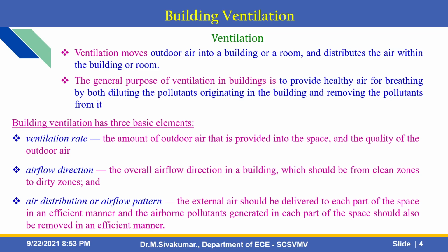What is the ventilation rate? It is the amount of outdoor air that is provided into a space, and the quality of the outdoor air. As for airflow direction, the overall airflow direction in a building should be from clean zones to dirty zones. And what is the air distribution or airflow pattern? The external air should be delivered to each part of the space in an efficient manner, and the airborne pollutants generated in each part of the space should also be removed in an efficient manner. This is the concept of building ventilation.